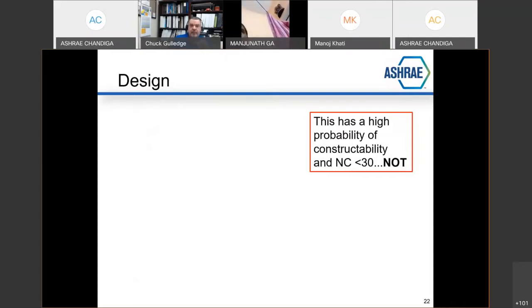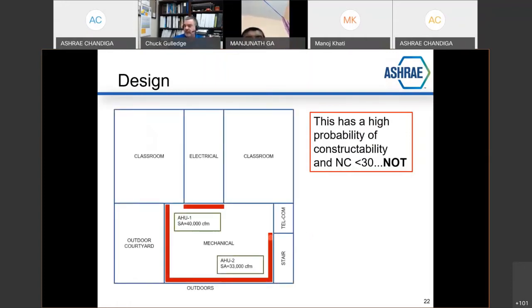This has a high probability of constructability and noise criteria less than 30. I don't think so. Take a look at this mechanical room. There's a classroom. There's a main electrical room. There's another classroom. There's another electrical room with all the telecom equipment. There's a stair. There's outdoors, and there's more outdoors. So these paths in red right here, there's no way to get ductwork for 73,000 CFM of air out into this building. You can't go through the electrical room with all the conduits going up and down. You can't go outside. You can't go through the egress area. And oh, by the way, somebody wanted to keep this.